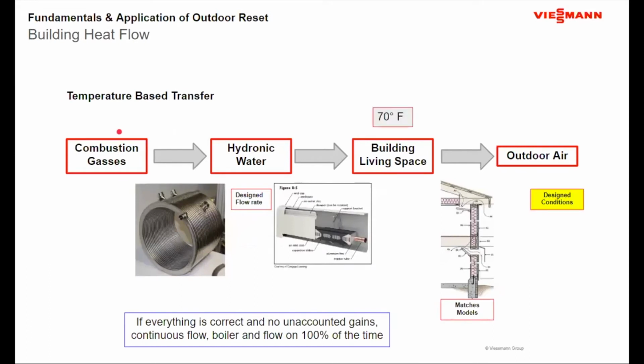So I come back here, my 70-degree room temperature, my 3,000 degree combustion gases. My outdoor temperature on the design day is going to be 0 degrees Fahrenheit. And based on my desire, I'm going to say I'm going to do 180-degree water temperature out to my baseboard. Then I'm going to make sure that I'm flowing at the right rate and I have enough baseboard in that house so that with 180-degree water at design flow rate, I am putting the right amount of energy into the living space that on a 0-degree day, it matches the energy that the building is losing to the outside. So that becomes our goal really in this design process.